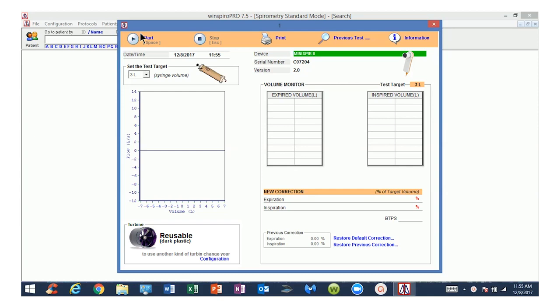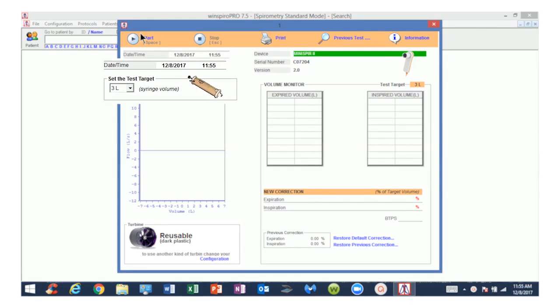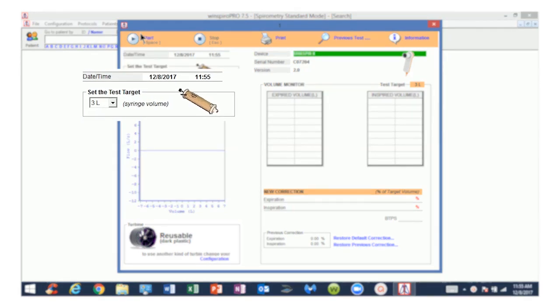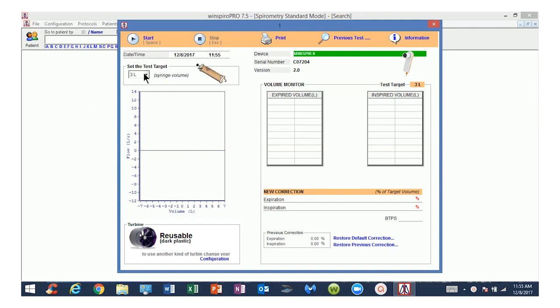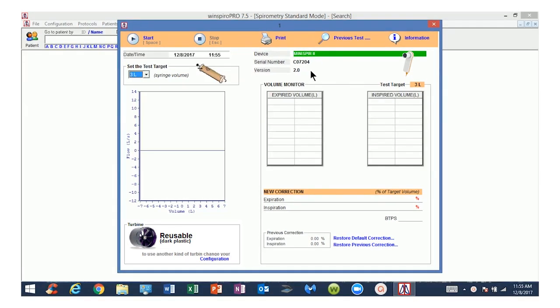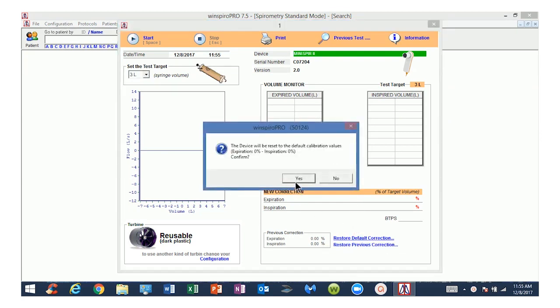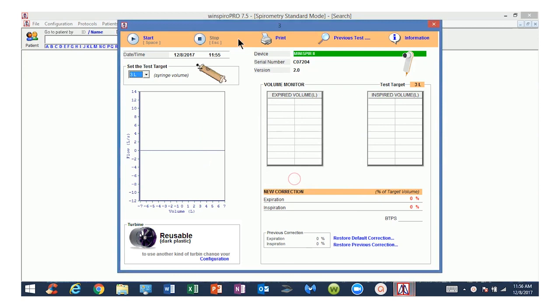Below the row of icons on the calibration test screen, you will see the date and time automatically entered. Below the date and time, you will see the Set the Test Target. From the drop-down arrow, select the volume of the syringe you are using. In this video, we are using a 3-liter syringe. To the right of that, you will see the device that is connected with its serial number and firmware version. In the lower right corner, click Restore Default Correction and prepare the syringe by pulling the piston out fully.